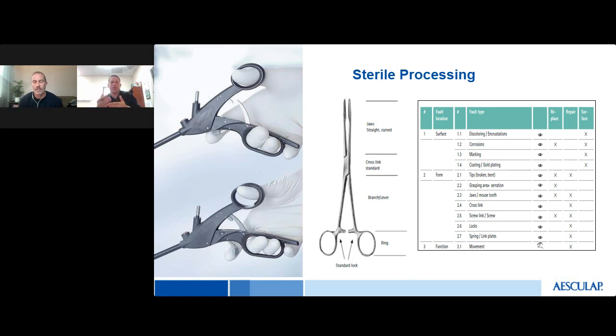The instrument was, and I don't know how old this instrument was, but it was put through use however many times, mixed within the sets. And again, if I had a chance to maybe see the instrument, the condition overall, maybe that would help me paint a better picture. But what I do know is that over time, just like everything else including instruments, that instrumentation is going to wear through the cycle of repetitive washes and sterilizations and use. And maybe that instrument had left and went for a repair somewhere, perhaps more than once over the course of however many years, depending on how old the device is. Again, it's a little bit hard to tell. There could be different variables to that, but it could be compromised throughout all these stages somewhere.